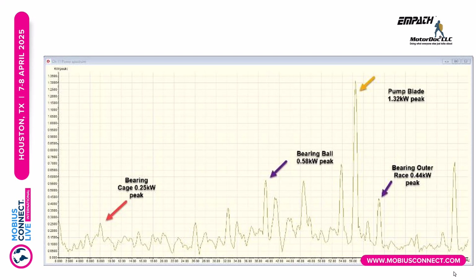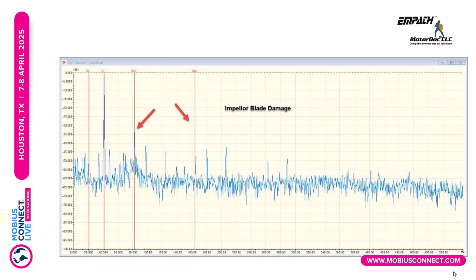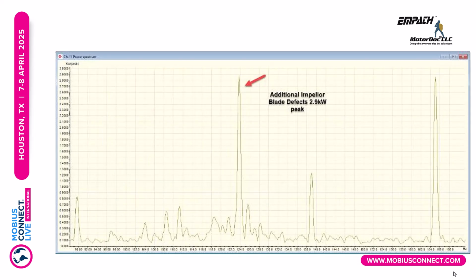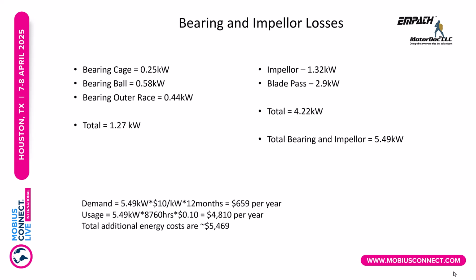Here's the losses associated with the bearings. So when we add those together, plus the pump blade, so 1.32, that turned out to be a nick in the blade. Somebody must have dropped it when they were putting the pump together. The cage, quarter kilowatt, 250 watts. The ball bearing, 580 watts, and the outer race, 440 watts. There is that impeller blade damage, which is an additional 2.9 kilowatts. We add all that together, that's 5.5 kilowatts worth of damage to that machine.